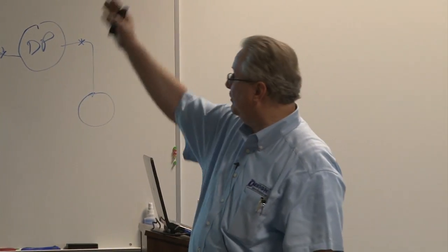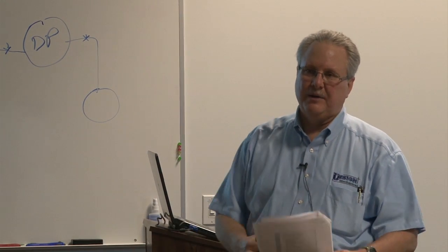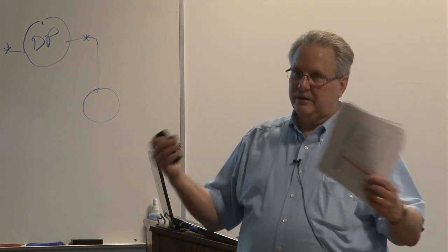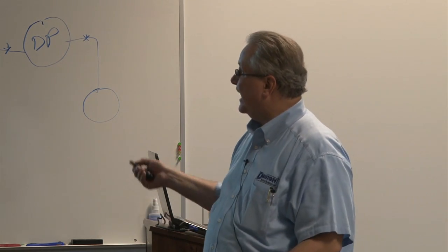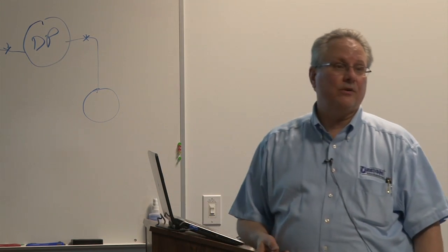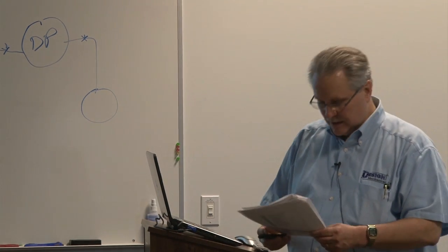But again, the problem is, here's a printout of that snapshot today, here's another piece of paper of tomorrow. Unless someone takes that and puts it on a log where you can just look right there and see trends, it doesn't help you that much. But there are more and more manufacturers offering extra front ends, programming, or interfaces to capture this. It's worth asking that question of your chiller manufacturer.